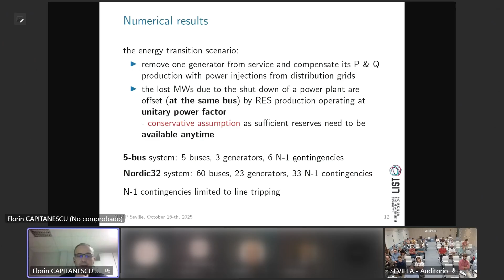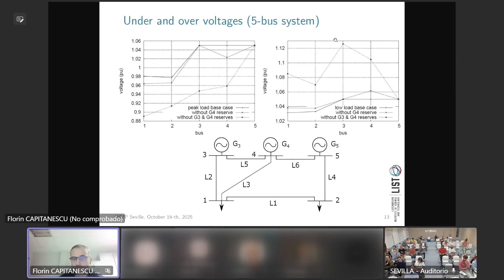Obviously, when you take these 2 things out, you remain with only 1 generator, and here you can see the voltages in absorption node, that all voltages drop and drop below 0.9, okay, in this node here, which is the farthest away from G5, you have bad voltages already, so it's the time where the operator should start thinking about improving the reactive power. Now, on over voltage issue, so again, at light load, you see that once you start losing voltage control, so you don't have any more this generator, so voltage plans start to rise, right?